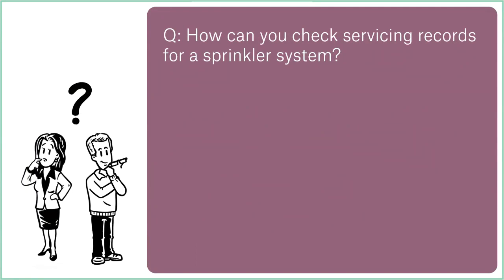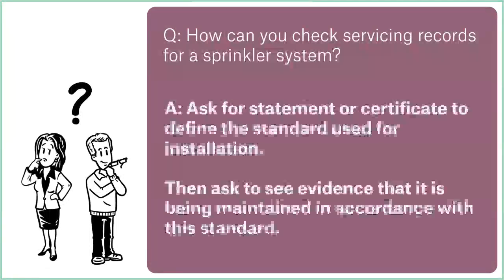Okay, I don't know how many questions I've got left. How can you check servicing records for a sprinkler system? Really, you just need to ask for them. Again, how it should be serviced is another question. And again, it should be serviced in accordance with the standard that it was installed to. So code standards will have a section on service and maintenance, and that is the minimum. Okay, all the time we're talking about minimum. So I mentioned earlier about flow switches being tested quarterly. That's the minimum. Okay, they can be tested more than that.